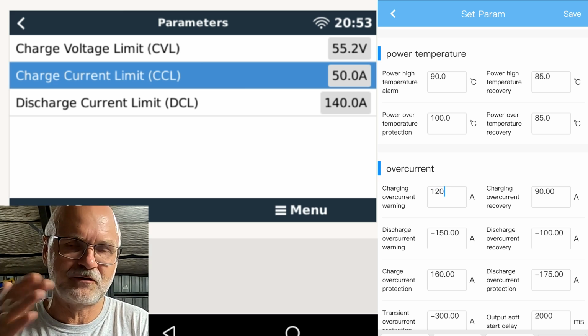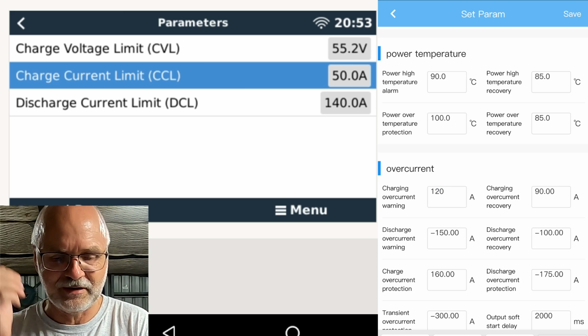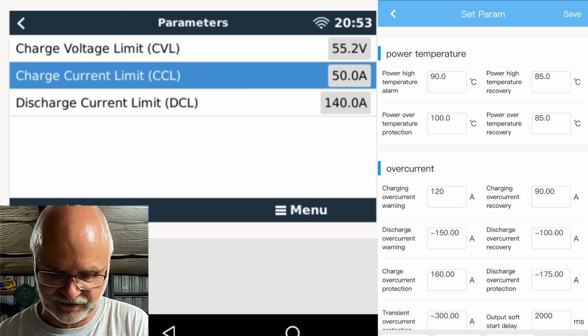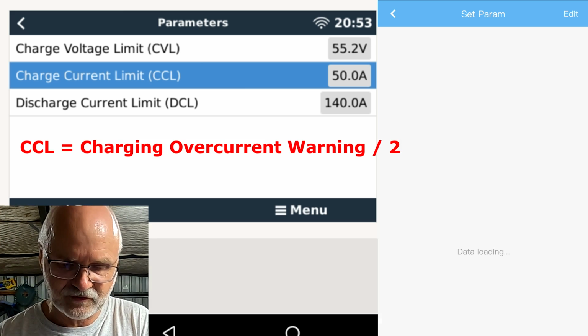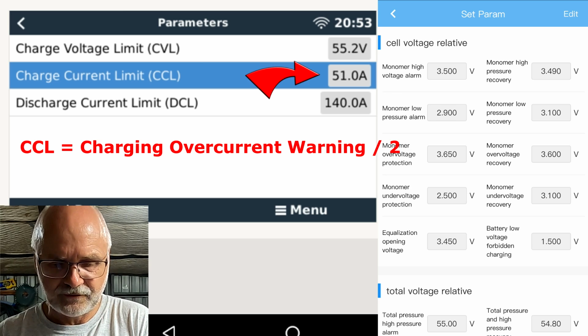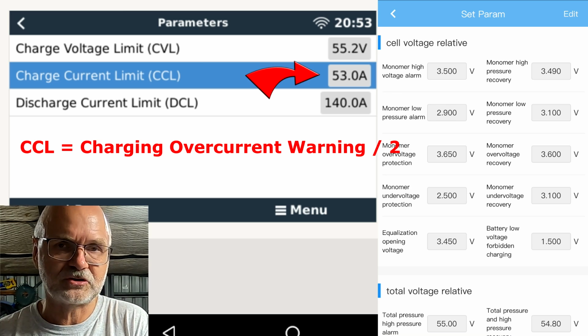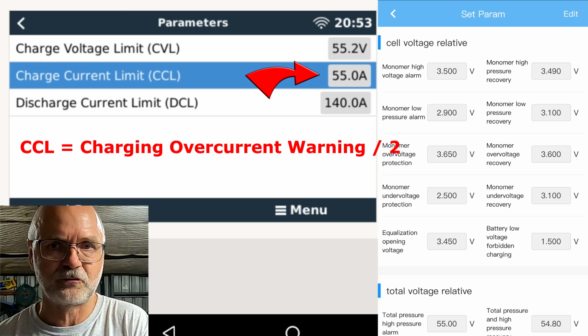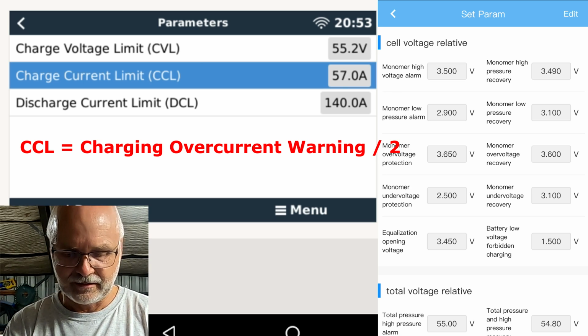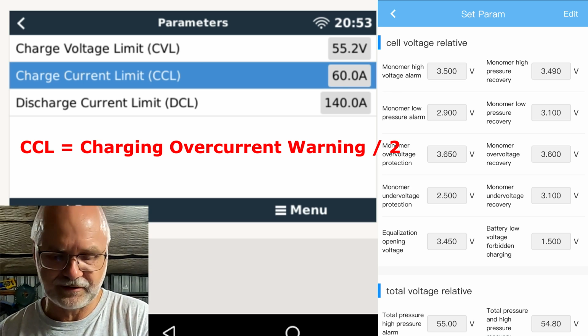120 amps divided by 2 is 60 amps. So we'll see the charge current limit will go up to 60 amps once we save this parameter. Success, and now you can see the charge current limit is increasing from 50 to 60 amps. So this is how you set the charge current limit.